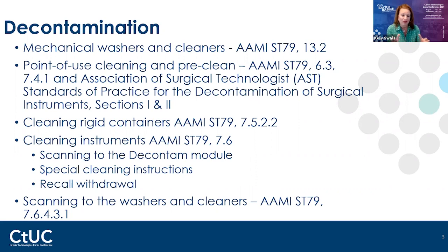Along with that, if that container is part of a recall, so for example, if you had a wet load, and so you issued a recall for all your instruments, and as you issue this recall, everything in that load is now flagged, returned to sterile processing, this item's been recalled. Well, if that set has been scanned to the decontam module, that alert will be withdrawn. So staff aren't going to have that. And so now you're kind of narrowed down, you know, how many sets you need to find, and they're not going to get that recall every single time it's scanned, because it's been sent to decontam, and thinking of it as decontam always restarts the cycle.